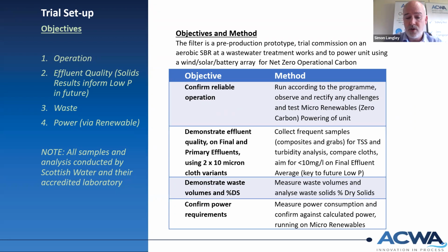We also wanted to demonstrate the waste volumes that are typically always less than 1% of the feed flow in our machines, which is a factor of 10 times lower than water-based systems, and to analyse the percentage dry solids coming off the unit. And it's also to confirm the very low power usage requirements that our system has. Because it's air cleaned and very static, it doesn't take a lot of backwash pumping, and also to run stably off the micro renewables over the trial. Just for the benefit of everyone, the sampling and analysis was conducted by Scottish Water and their accredited laboratory.